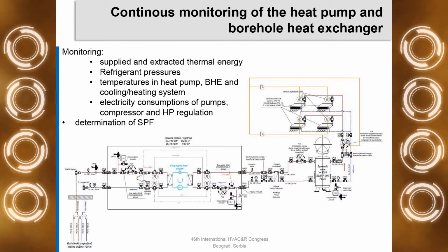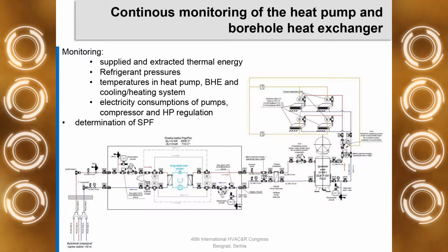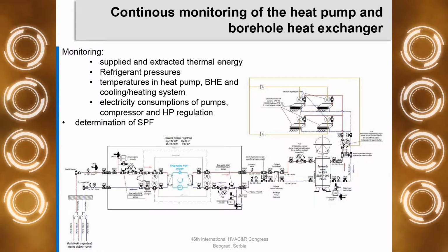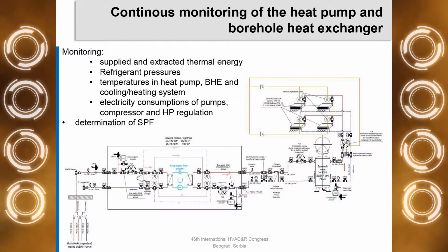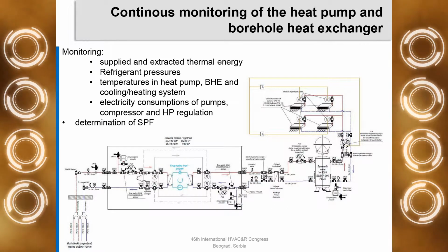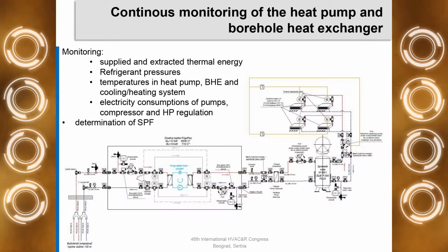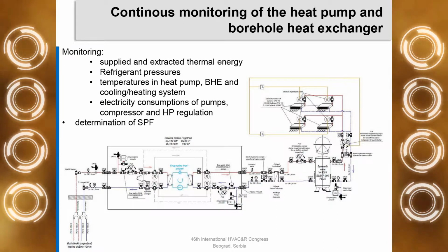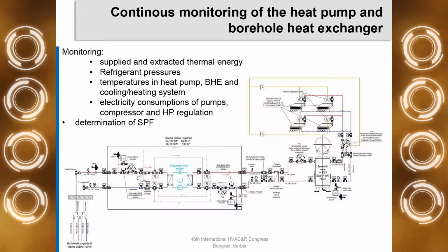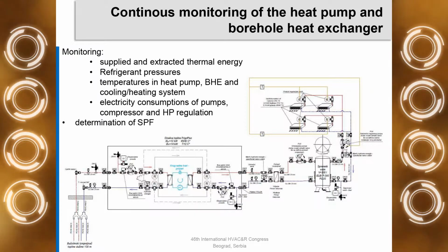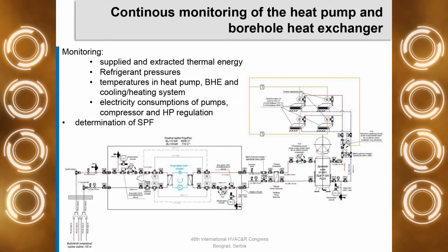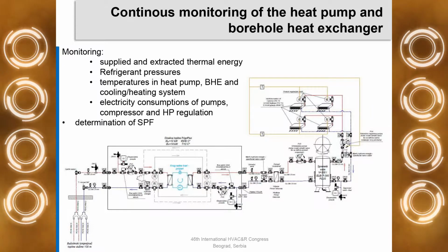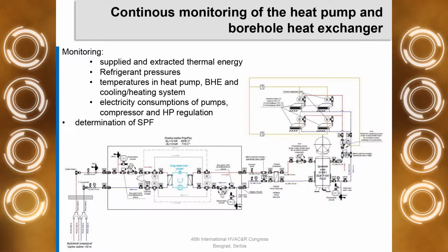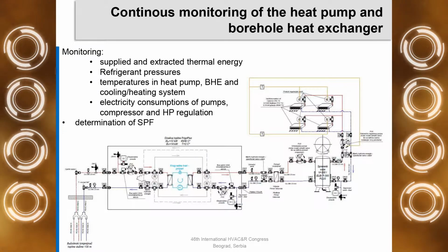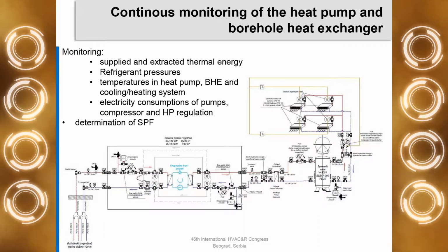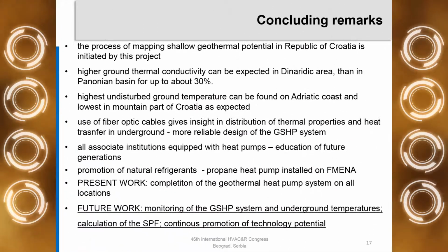This is a schematic diagram of our system. The borehole heat exchanger is installed, and the heat pump was connected. A few days ago, we completed the installation of the fan coils and distribution system. In the days to come, we will install electricity and connect all the components and run the system for the first time, basically by the new year. Also here we installed a compact heat exchanger because the heat pump is reversible on the water side. We wanted to prevent the glycol and water mixture from entering the conditioned spaces, because since we have around 150 liters of accumulation, we would need a large amount of glycol, and that was not very affordable. So that is the system that we will have operational soon on our faculty.